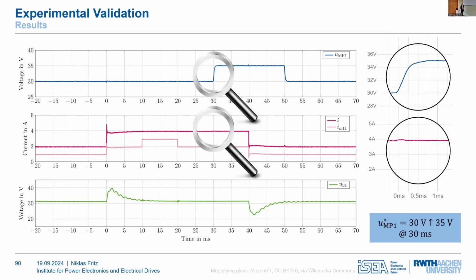You can also change the reference for the midpoint voltage, which is now this closed loop voltage control, and you can see that the step change is quite nicely followed here by the midpoint voltage, but the terminal current is not affected. So those variables are fully decoupled.